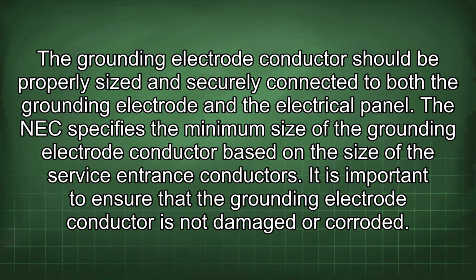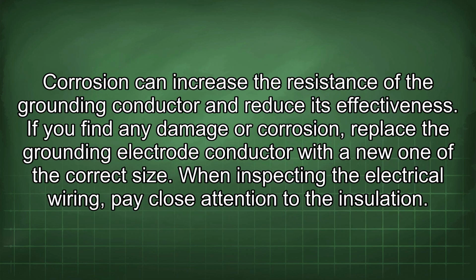It is important to ensure that the grounding electrode conductor is not damaged or corroded. Corrosion can increase the resistance of the grounding conductor and reduce its effectiveness. If you find any damage or corrosion, replace the grounding electrode conductor with a new one of the correct size.